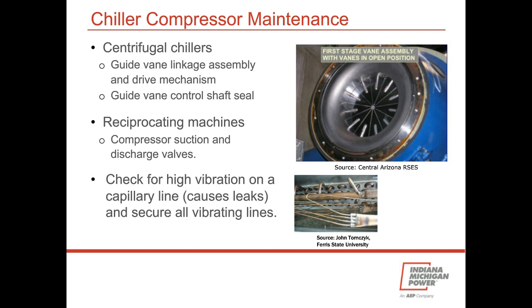And then reciprocating machines, you have compressor suction discharge valves that open and close. And then in some cases, for simple refrigerant metering, you'll use capillary lines like this. That's in lieu of thermostatic expansion valves. Probably more seen on RTU units, but they're pretty long, 5 to 15 feet, very slender tubes, brazed, and with vibration can leak or crack and malfunction. So inspection of those is important too.